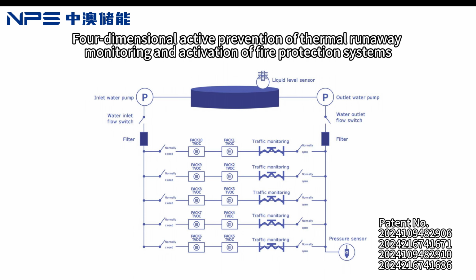After the system confirms the thermal runaway, the temperature control fire module will automatically open the normally closed solenoid valve on the water inlet side of the thermal runaway battery box, and at the same time close the pipeline solenoid valve of the unaffected battery boxes. The inlet and outlet pumps start to work, injecting the firefighting solution into the battery box where thermal runaway occurs, and carrying out cooling, liquefaction, adsorption, filtration and recycling of the erupted electrolyte fumes, so that the fumes do not leak out and there is no risk of explosion and fire.